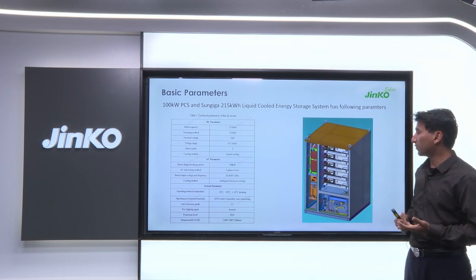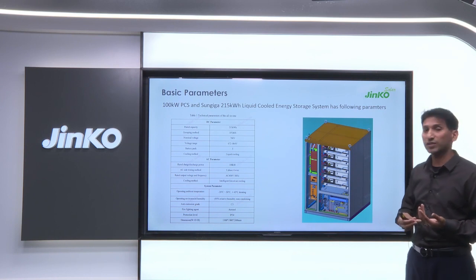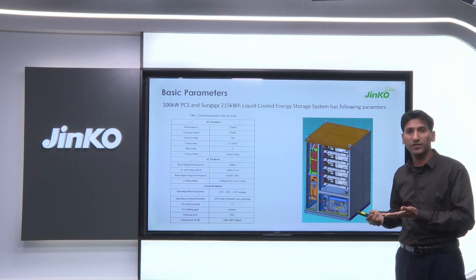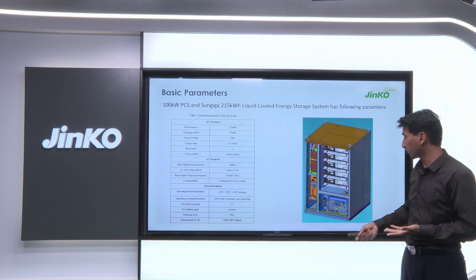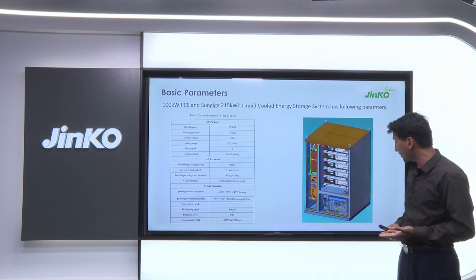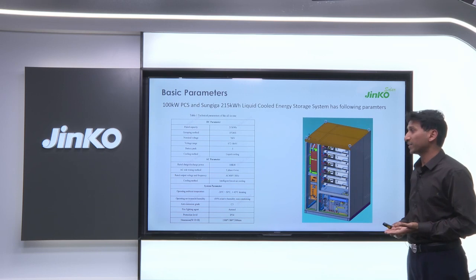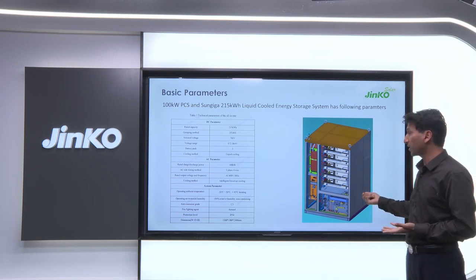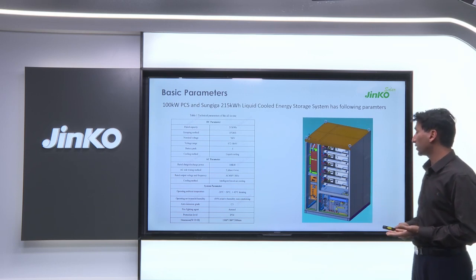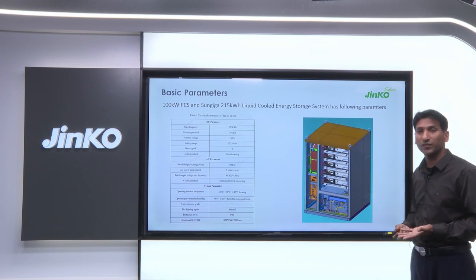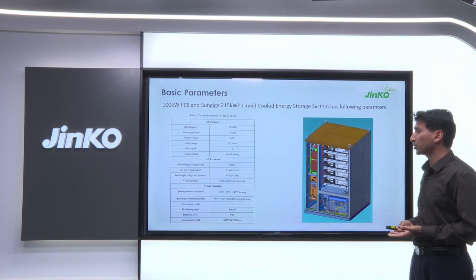AC parameters, the second one, are related to the part which converts DC into AC. That must be an inverter. Down there, we have an inverter which is 100 kilowatt, with a 3-phase 4-wire connection: 3 phase, 1 neutral. The output voltage of the PCS is 400 volt for three-phase, and for single phase it is 220 volt.